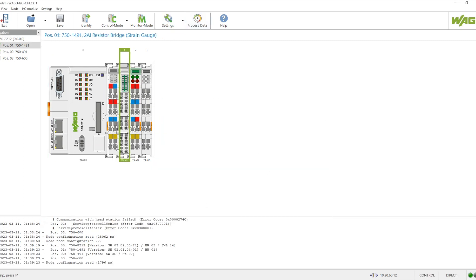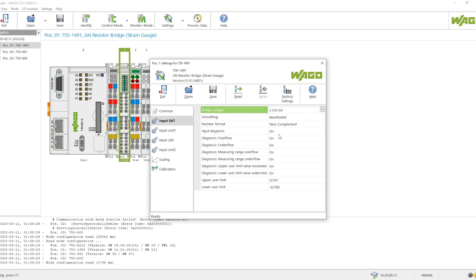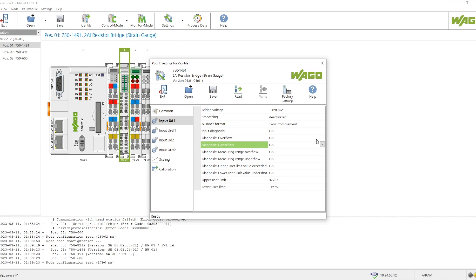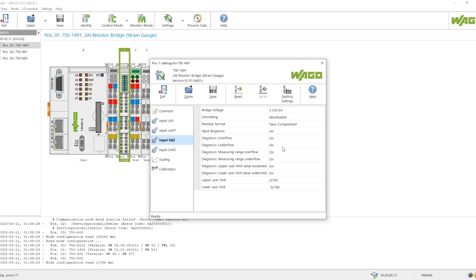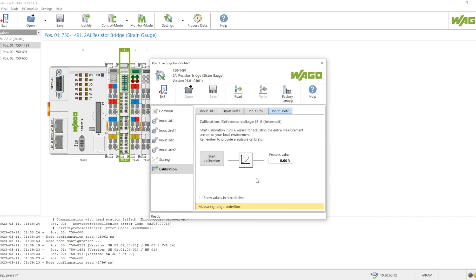When we click on an IO card, its settings get enabled and we can configure the different IOs. All configuration parameters are shown here — for example, whether smoothing should be activated or deactivated. We can set the reference voltage; I am using a strain gauge card here. We can also run linear scaling and perform calibration by clicking 'Start Calibration' — all of that is possible directly using WAGO IO Check.